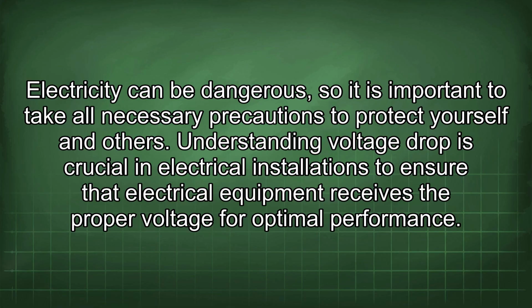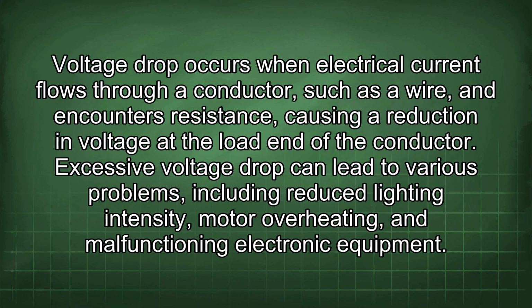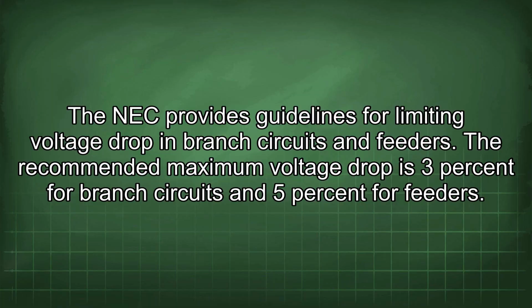Understanding voltage drop is crucial in electrical installations to ensure that electrical equipment receives the proper voltage for optimal performance. Voltage drop occurs when electrical current flows through a conductor, such as a wire, and encounters resistance, causing a reduction in voltage at the load end of the conductor. Excessive voltage drop can lead to various problems, including reduced lighting intensity, motor overheating, and malfunctioning electronic equipment. The NEC provides guidelines for limiting voltage drop in branch circuits and feeders.